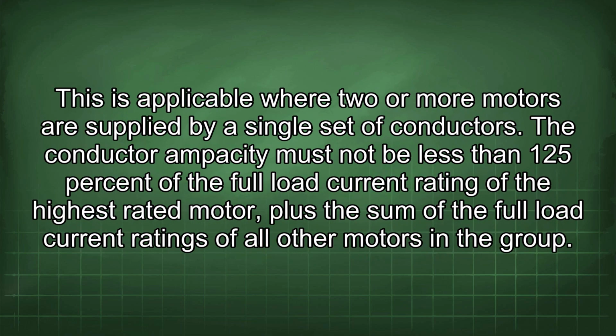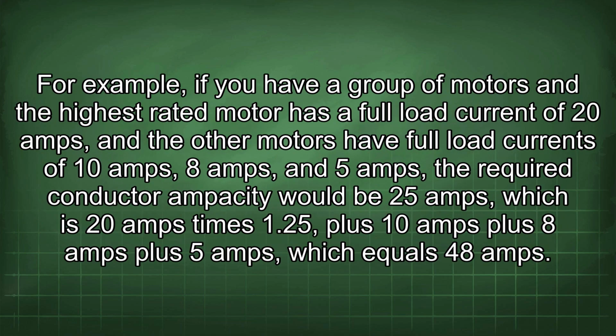This is applicable where two or more motors are supplied by a single set of conductors. The conductor ampacity must not be less than 125% of the full load current rating of the highest rated motor, plus the sum of the full load current ratings of all other motors in the group. For example, if you have a group of motors and the highest rated motor has a full load current of 20 amps, and the other motors have full load currents of 10 amps, 8 amps, and 5 amps, the required conductor ampacity would be 25 amps, which is 20 amps times 1.25, plus 10 amps plus 8 amps plus 5 amps, which equals 48 amps.